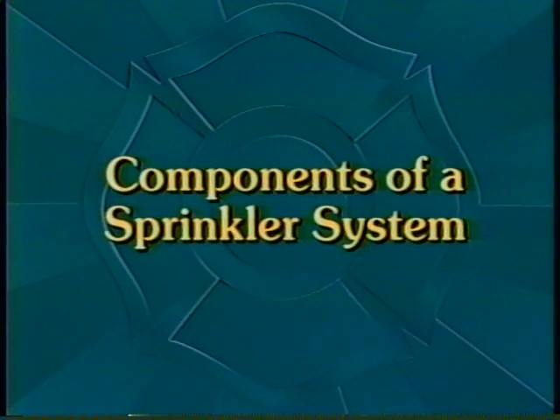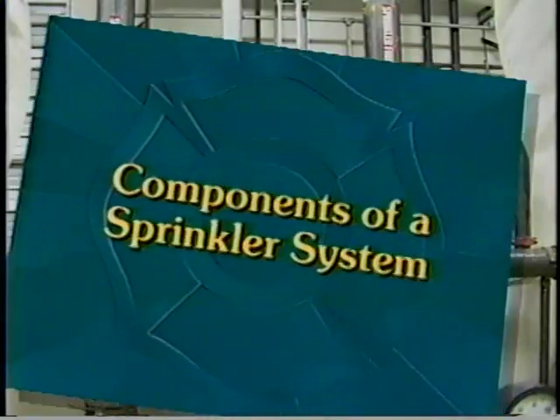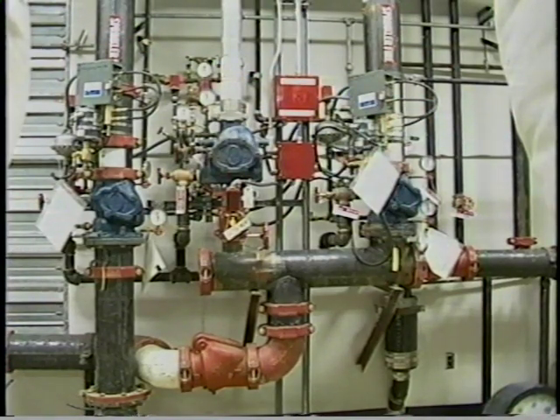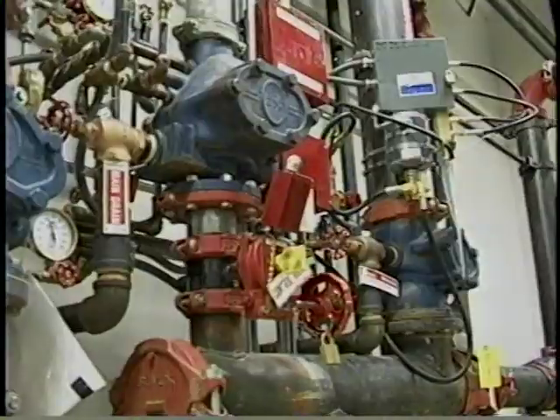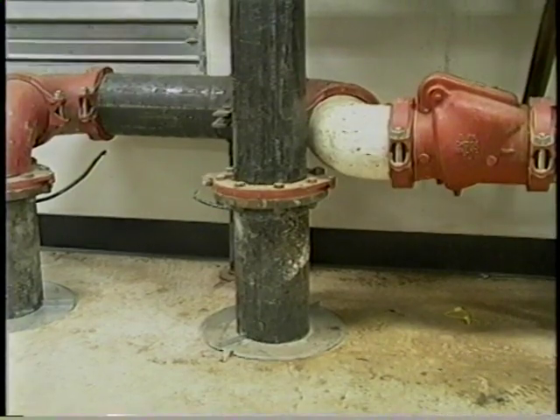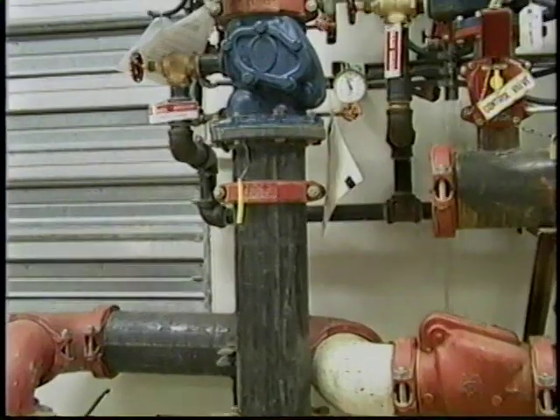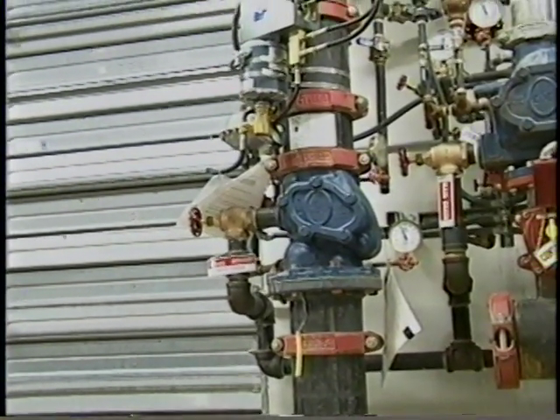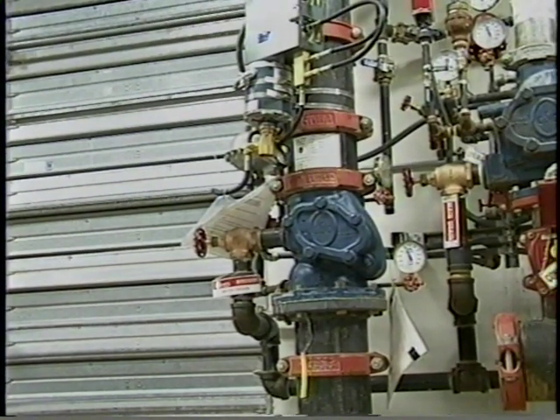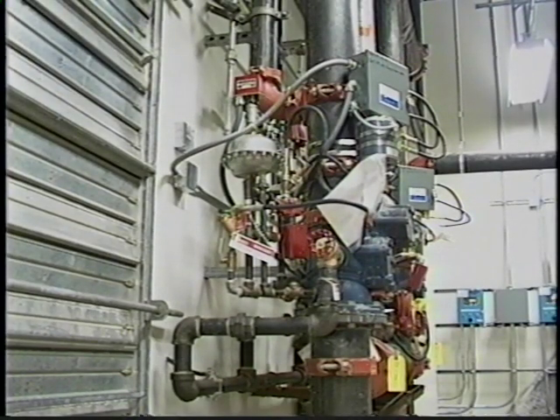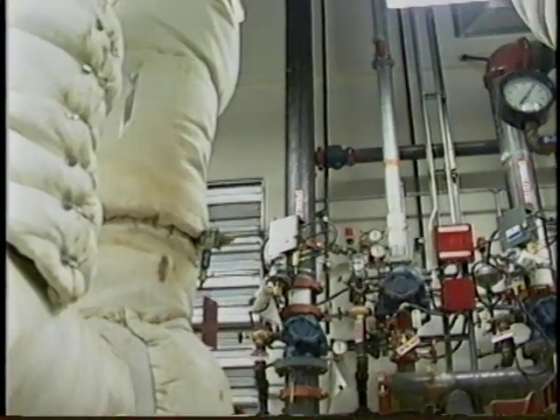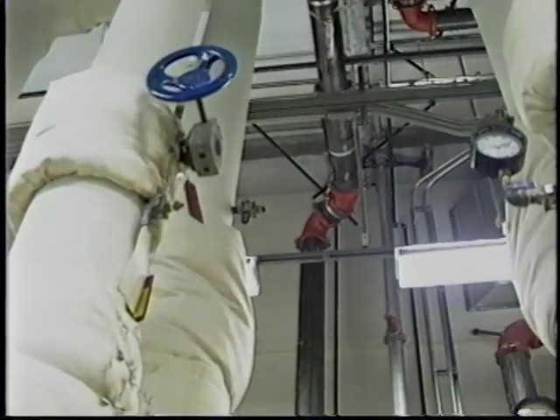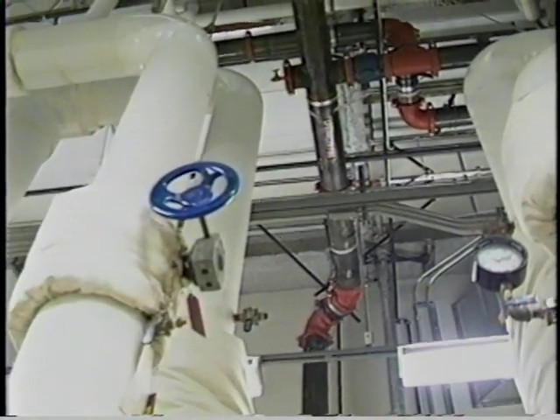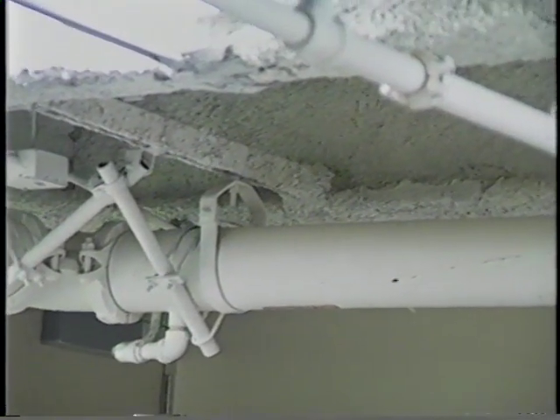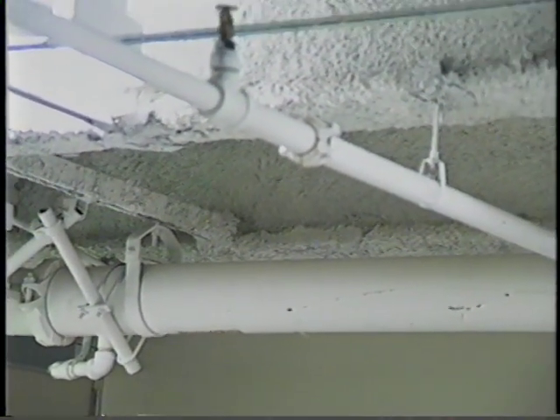In order to properly operate an automatic sprinkler system, it is important to understand the system's components. The system starts with a feeder main into the sprinkler valve. The riser is the vertical piping to which the sprinkler valve, one-way check valve, fire department connection, alarm valve, main drain, and other components are attached. The feed main is the pipe connecting the riser to the cross mains. The cross mains directly service a number of branch lines on which the sprinklers are installed.